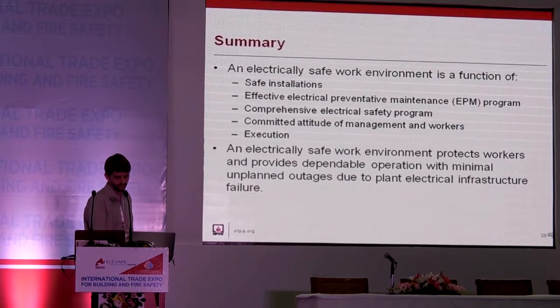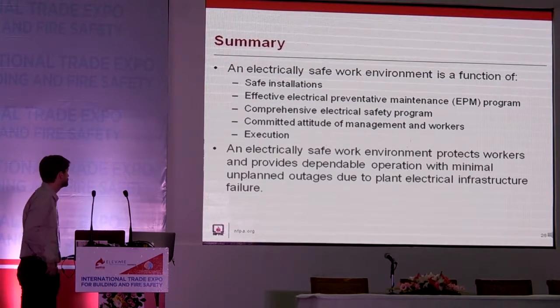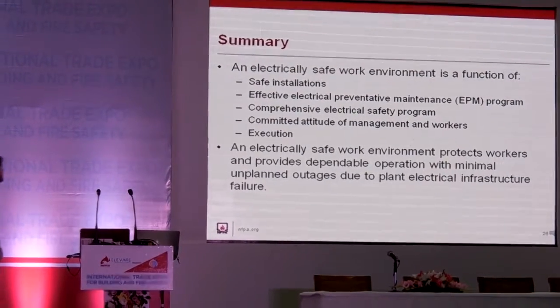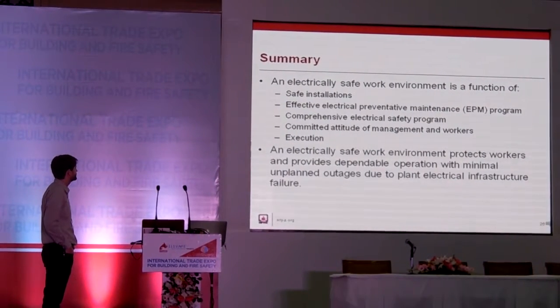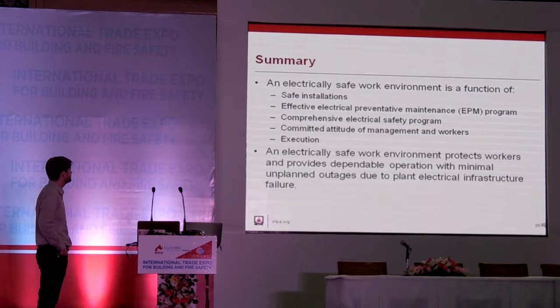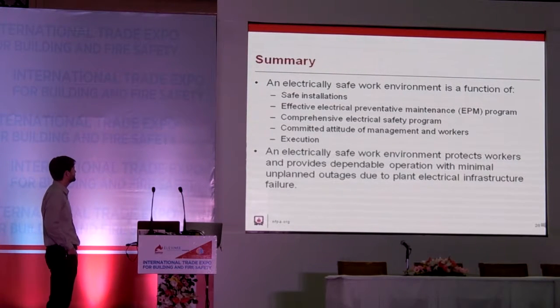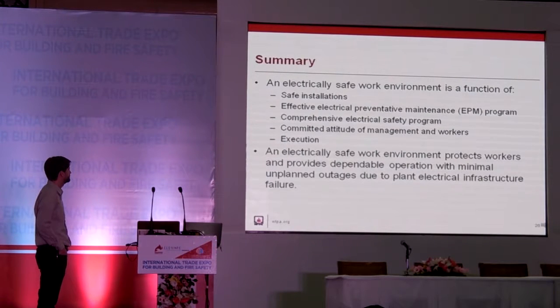Several key factors contribute to an electrically safe work environment, beginning with safe installations that are performed in accordance with recognized installation codes and standards, and also in accordance with any instructions and recommendations that are part of the product certification or are provided by the manufacturer, is the starting point. Maintaining that equipment in accordance with the manufacturer's instructions and also recognized electrical industry standards helps to ensure the ongoing operation of the equipment and, more importantly, the ongoing safe operation of the equipment.